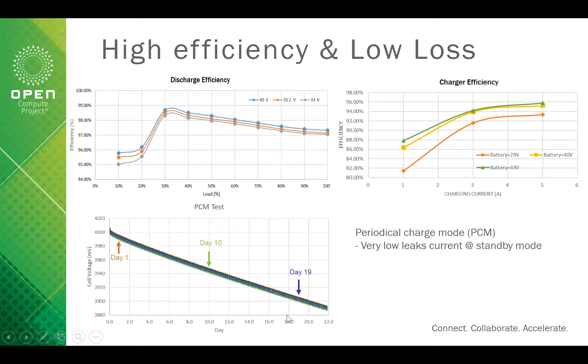When we do the dynamic load at the power shelf level, for example, we put 5 BBU in the power shelf, then we do the power shelf, BBU shelf dynamic load. We can check 10% to 100%, or 50% to 100%, or 20% to 150%. We can see the minimum voltage is higher than 96.5 volts.